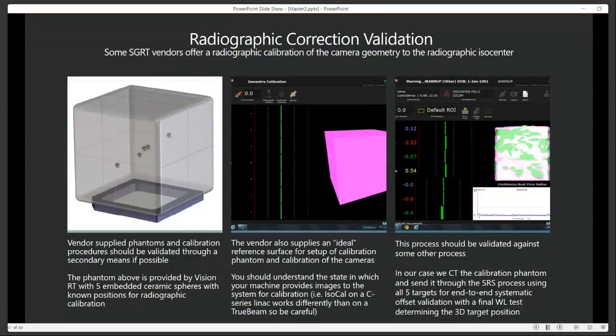Radiographic calibration, again, is an interdependent calibration step for our cameras in the system that we have. The vendor provides a very highly accurately machined Phantom, down to thousandths of an inch or tenths of millimeters. And so it has 5 ceramic spheres, allows you to take images and determine the 6-degree orientation of that Phantom. They also give you an idealized surface and say, line it to the idealized surface, take the images, and then do a radiographic calibration by processing the correction between the images and your mechanical calibration. It's a very elegant process. It's very clean and easy.